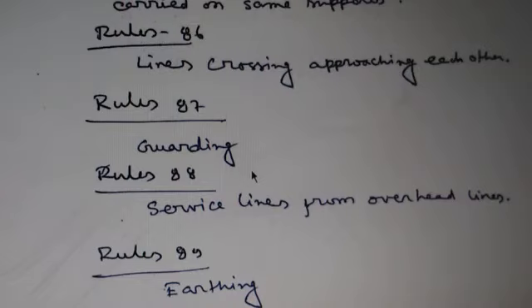Next point, line crossing trolley wires. In the case of crossing over trolley wires, the guarding shall fulfill the following conditions. First condition, where there is only one trolley wire, two guard wires shall be erected.